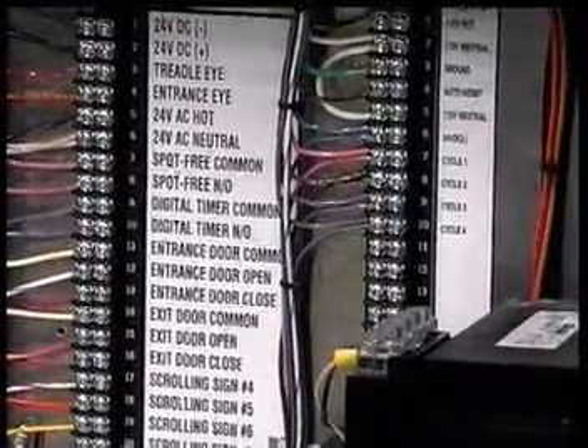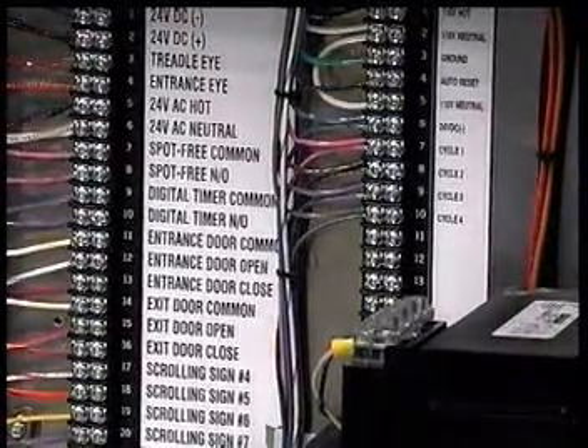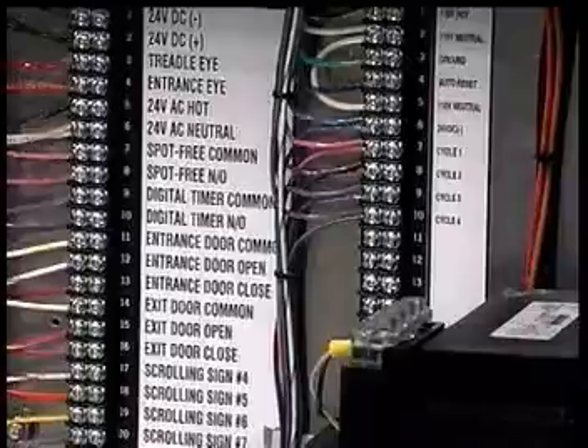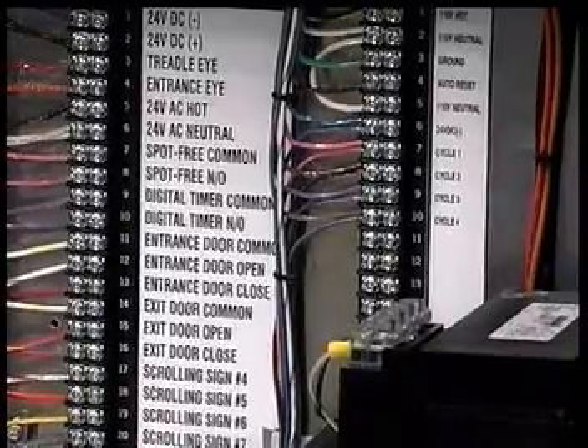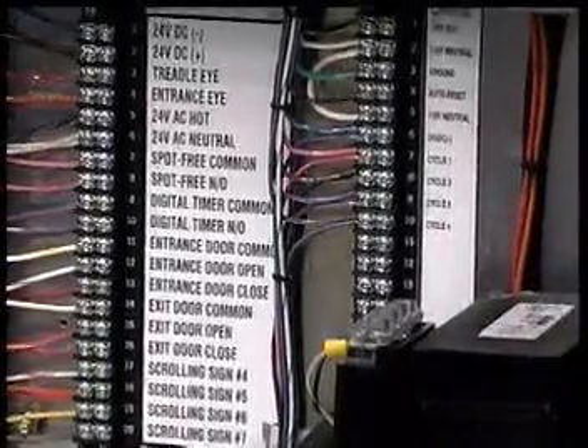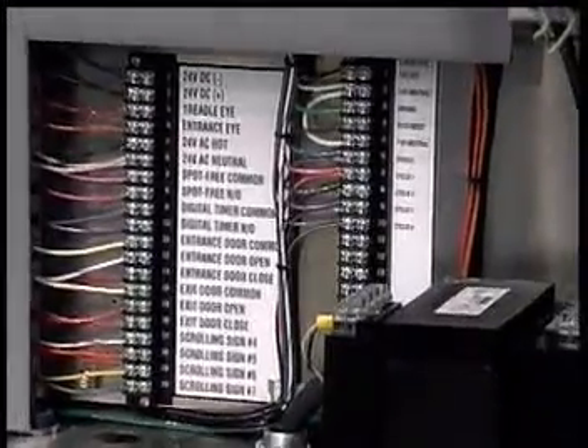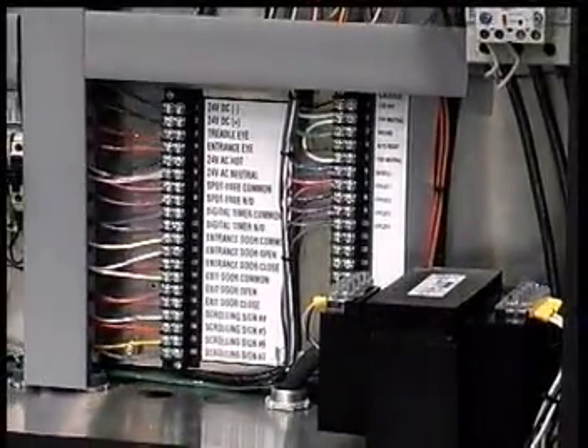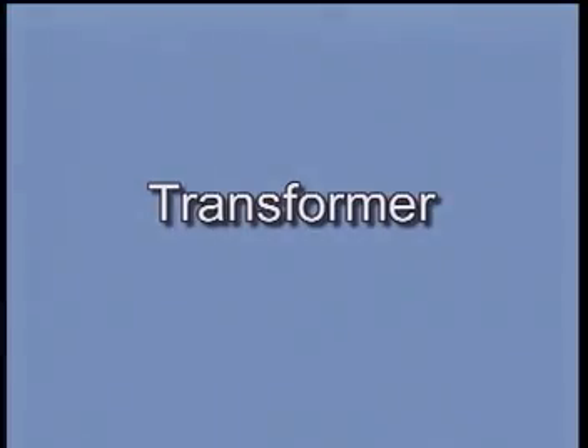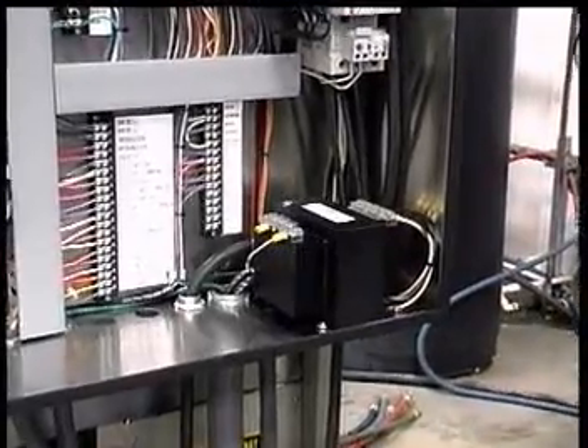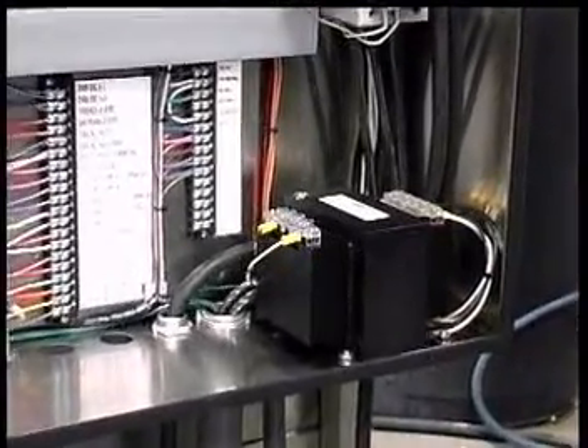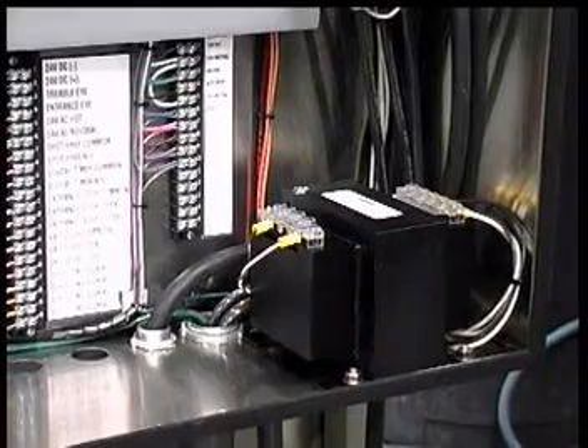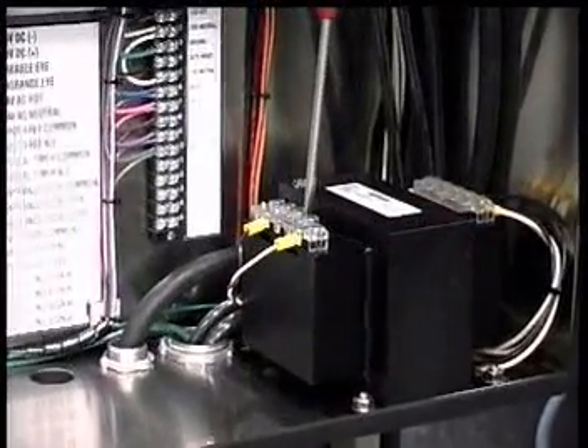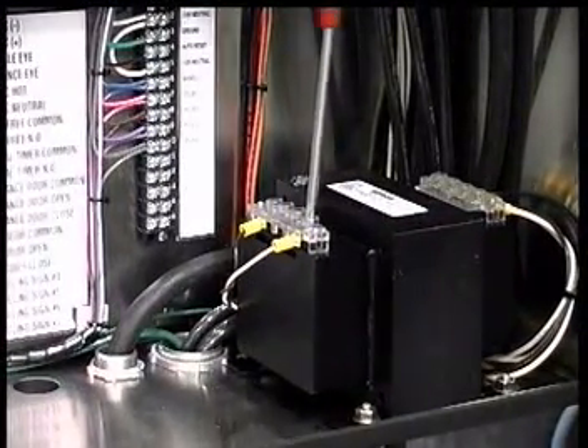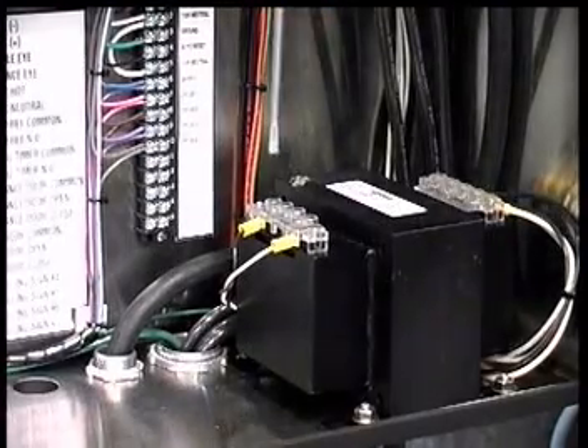Terminal strips in the control panel are well marked for easy wiring. As with any terminal connection, make sure only the bare wire is under the connection with no stray wires touching other terminals and that all connection screws are tight. The transformer will convert the 110 volt power to 24 volt. Make sure all connections are tight. Test proper operation with a voltmeter using guidelines in Chapter 13.